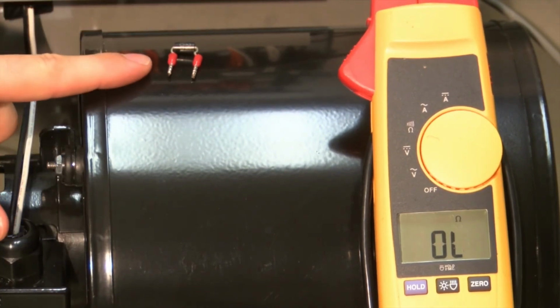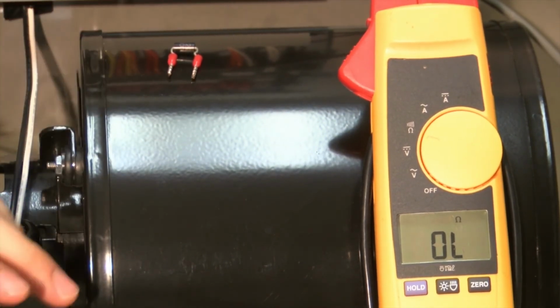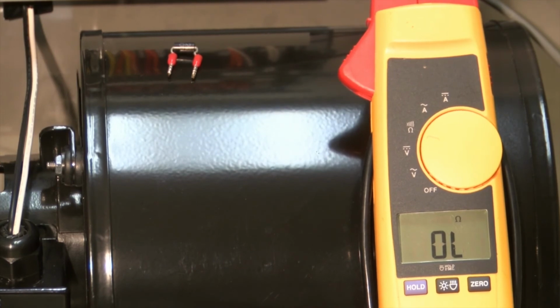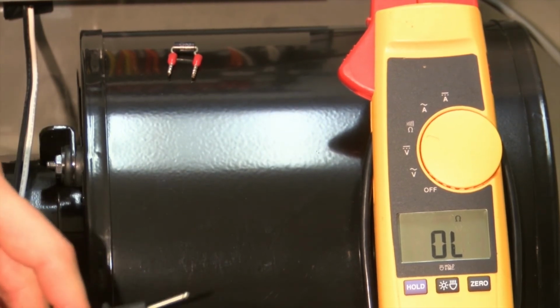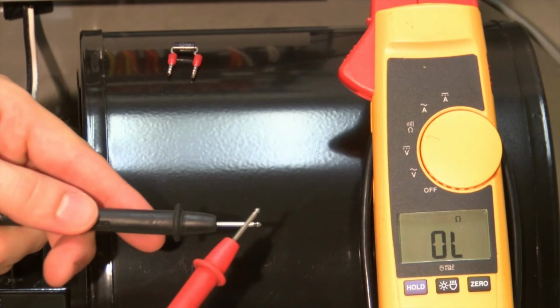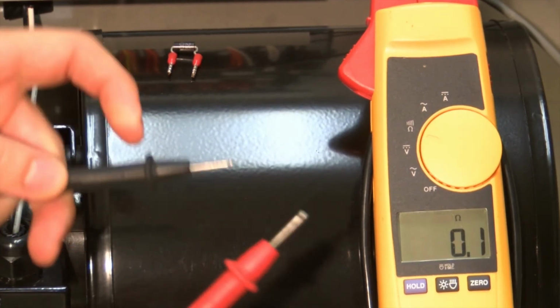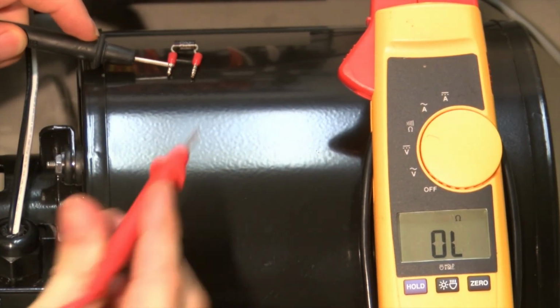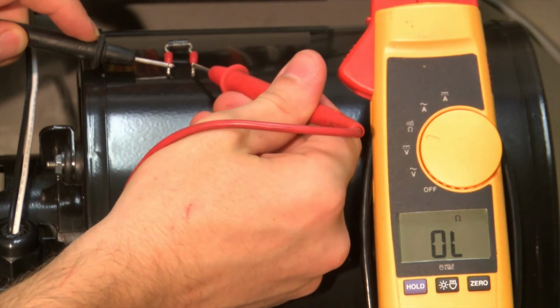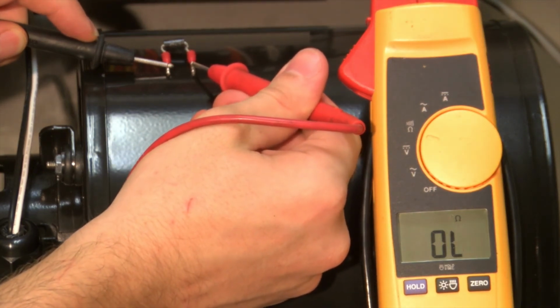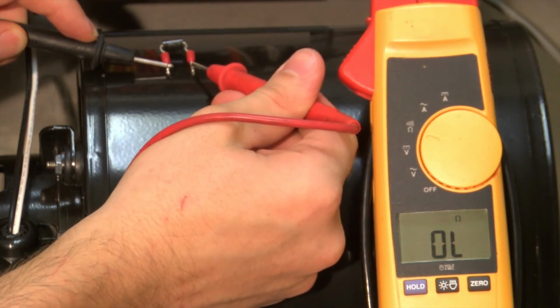To check a surge arrestor, you want to check for continuity across it. A good surge arrestor will not have continuity across it. When a surge arrestor is blown, it creates a short or continuity across it to blow the corresponding fuse. If you take your voltmeter or multimeter and set it on continuity, you can place one prong on each side of the surge arrestor. A good surge arrestor will not have continuity across it.